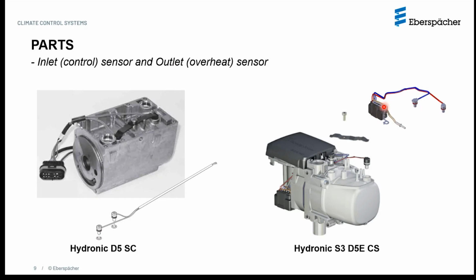Once again, before you tear down a heater, you first have to check whether the sensors are really defective. You can visually inspect them, and you can test the resistances. To test the resistance, you can use the connector. All you have to do is disconnect the connector from the ECU. You will see in later slides that there is a small panel on that ECU assembly that can be removed and will give you access to the connector, so you don't have to tear the whole unit apart initially. Once you have that panel off, you can unplug the connector and probe the appropriate pins to check the resistance for any of the sensors that belong to this assembly.